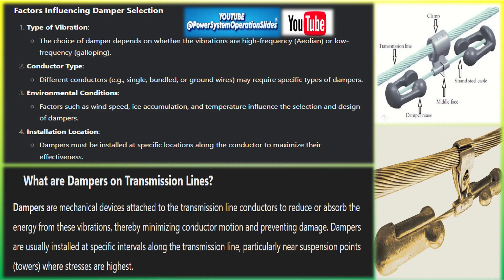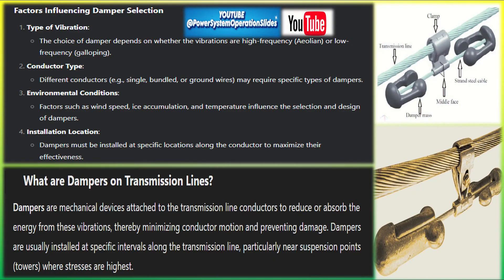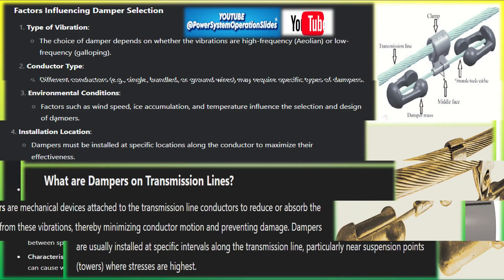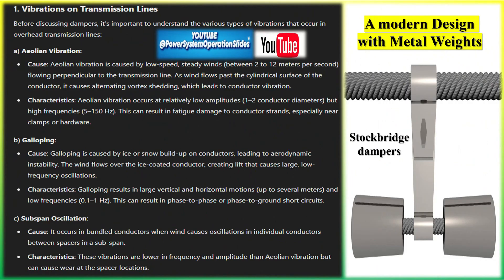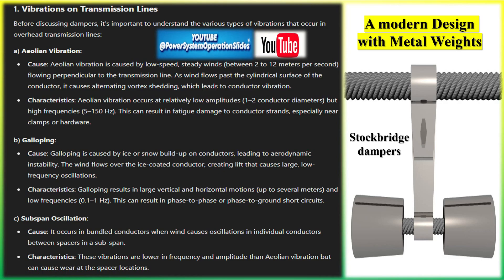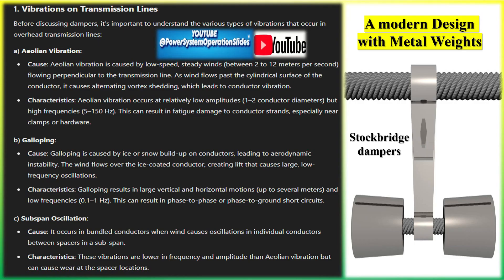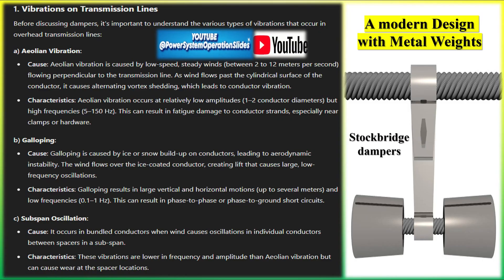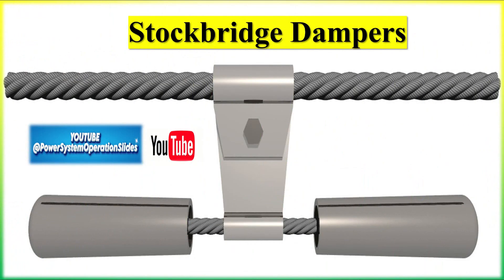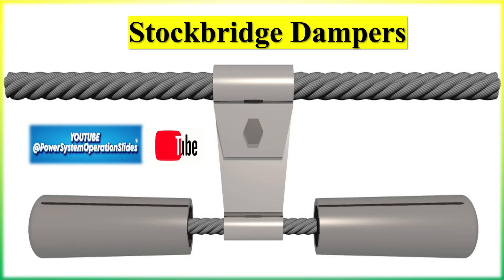There are several physical mechanisms involved. Dynamic absorption: dampers typically have a weighted mass connected to the conductor. As the conductor vibrates, the mass of the damper moves out of phase with the conductor's motion, causing the damper to absorb energy from the vibration and convert it into heat, thus reducing the vibration amplitude. Dampers are often tuned to specific vibration frequencies — for instance, dampers designed to reduce Aeolian vibration are tuned to respond to the high frequencies generated by wind-induced oscillations, ensuring they are most effective at reducing the particular type of vibration affecting the line.